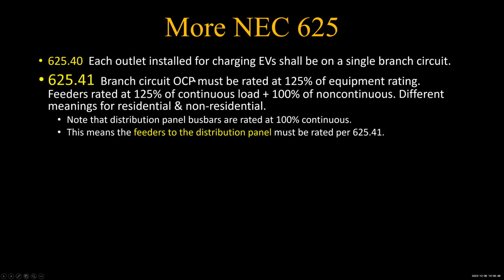We're coming to that. 41, this is the important one right here. Branch circuit overcurrent protection must be rated at 125% of the equipment rating. Okay, so you got a 40 amp charger, your branch circuit overcurrent protection is 125% of that, at 50 amps.